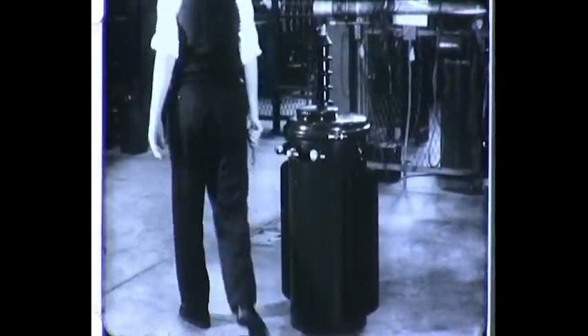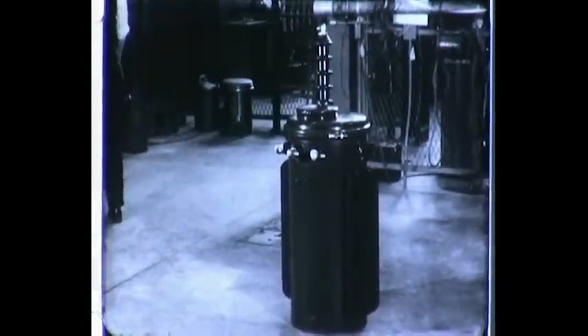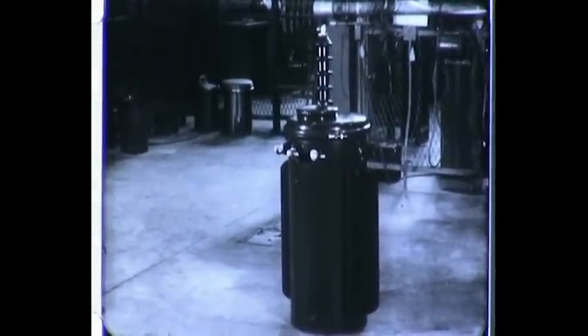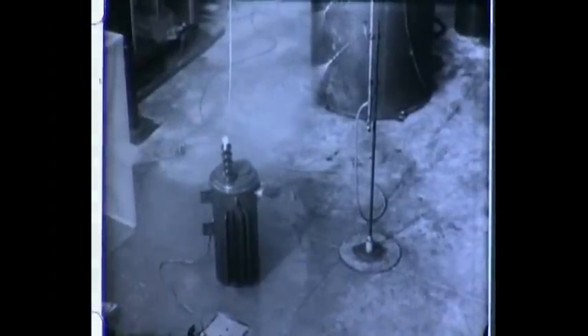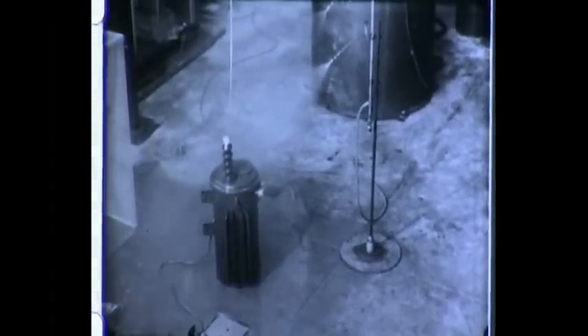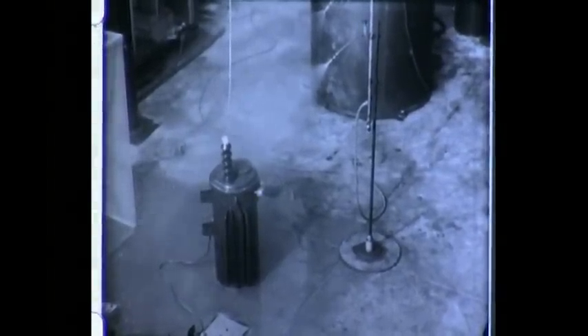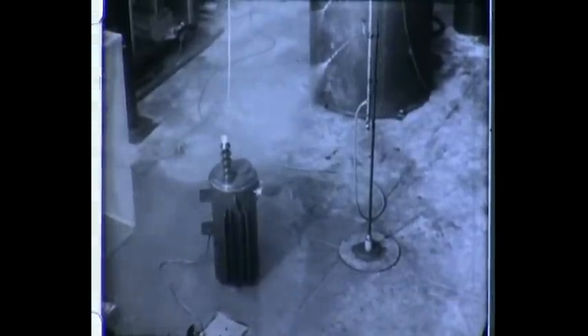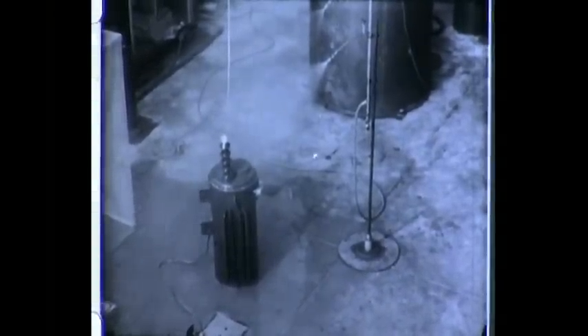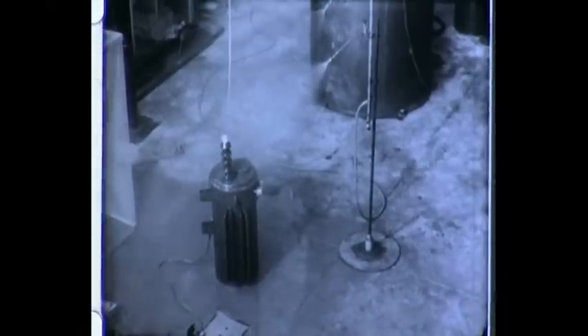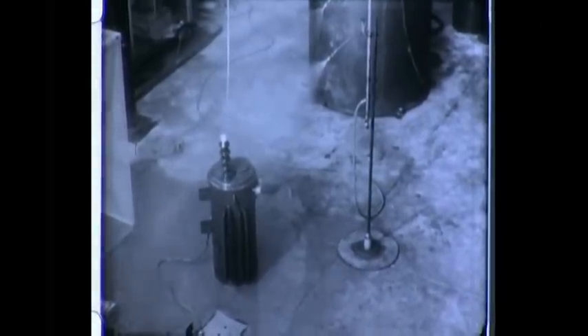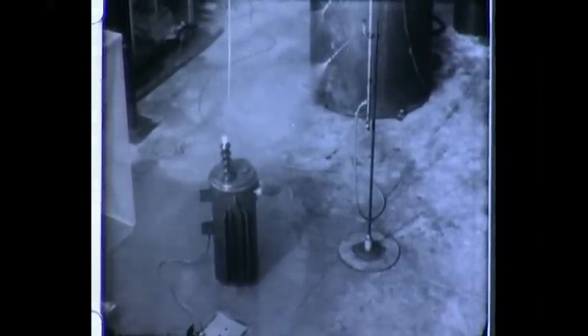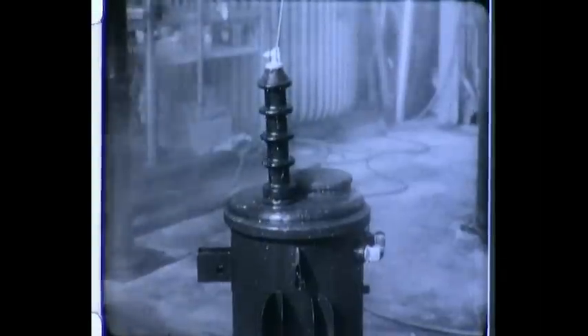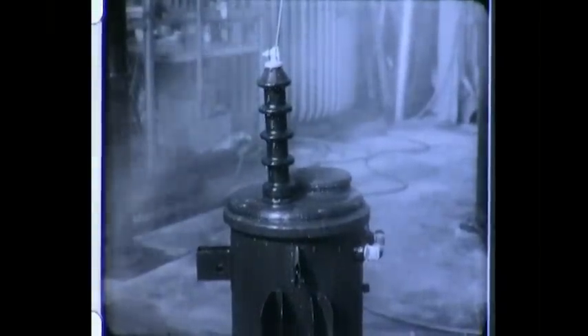At the Distribution Transformer Department, Pittsfield, Massachusetts, engineers test an experimental pole-type distribution transformer. In the high-voltage laboratory, the first test aims to find out how the new covers and bushings stand up under high electrical discharges. This test subjects the molded bushing and cover to wet flashovers of 50,000 volts at 60 cycles. Result: no tracking or damage to the molded materials.